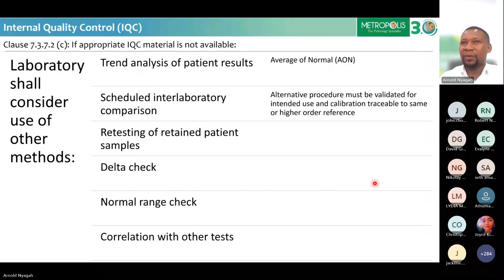Now, part D of this says that the tests have to be performed at a frequency that is based on the stability and robustness of your examination method. Okay, whether it is 2 controls per day or 2 controls per run. Okay, you need to check the stability and robustness of your examination method. And how do you check the stability and robustness of your examination method? You can check it easily by reviewing your coefficient of variation and checking your measurement of uncertainty, and also checking your total error.